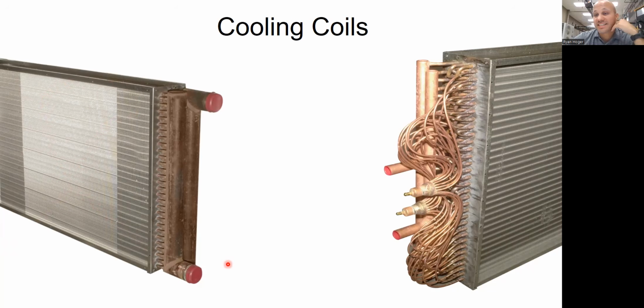If it is a DX system, direct expansion, there'll be a condenser on the roof, but you may not have been to the roof yet. You're just in the air handler room. And when you open up the door to the cooling coil, it will not look like this with a supply and return header. Instead, it'll look like this. It'll have all these distribution tubes. So the refrigerant will come into these distribution tubes, kind of like spiderwebbish almost, and has all these little tiny copper lines that go.